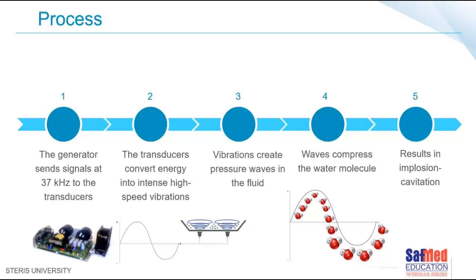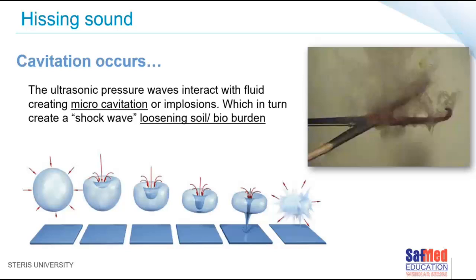What happens is that the ultrasonic generator sends a signal to those transducers. The transducers convert their energy into high-speed vibrations. And all of those vibrations create pressure waves in the water and fluid mix. The waves compress the water molecules, and when that happens, we end up with this implosion or cavitation process. So think about it now. You've all seen it, you've all heard the hissing. You switch the machine on, you hear that hissing sound. Now that's all of those hundreds and millions of little bubbles that are formed in the water. And when those bubbles collapse, they implode. Looking at the image over there, you can see the graphic of a water bubble now imploding. And when that implosion happens, it creates a bit of a shock wave. And that shock wave is what actually loosens all the soil and the bioburden. That's how they work.